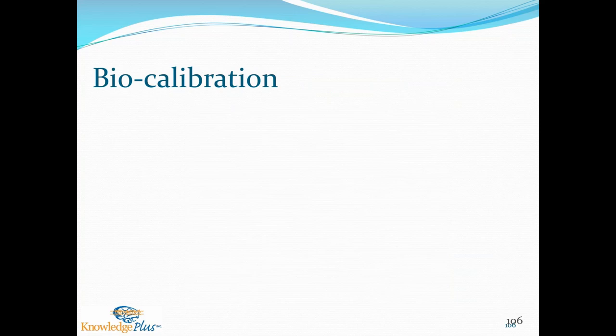Biocalibration, also not necessary. So to take FP1 to O2 on an analog EEG machine, you're feeding that same input into every amplifier. On a digital system, it's only one amplifier that you're checking. So there'd be no way it would be different channel to channel. So biocalibration, FP1 to O2, not necessary.